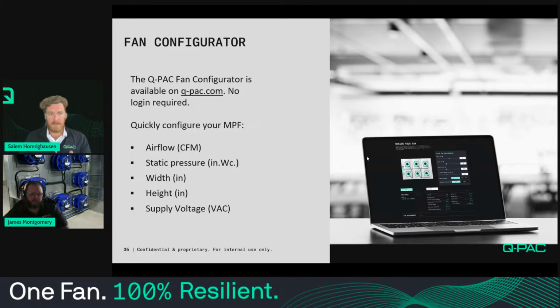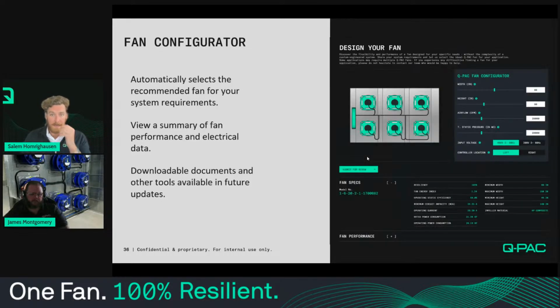You click design your fan, and then put in the airflow in CFMs, the total static pressure in inches of water column, your internal width and height in inches, and your supply voltage level - either 208, 230, or 480. Once you put those inputs in, you get a submittal you can print off for that particular MPF model, and you can even request a quote.